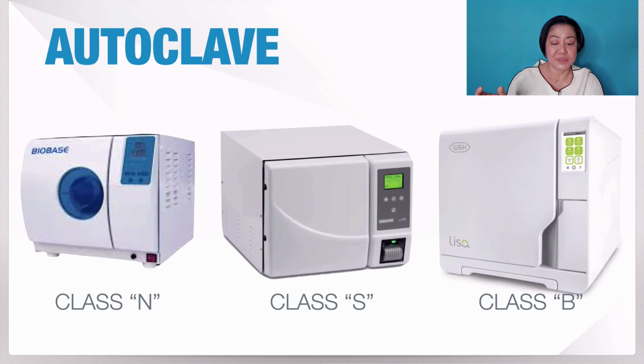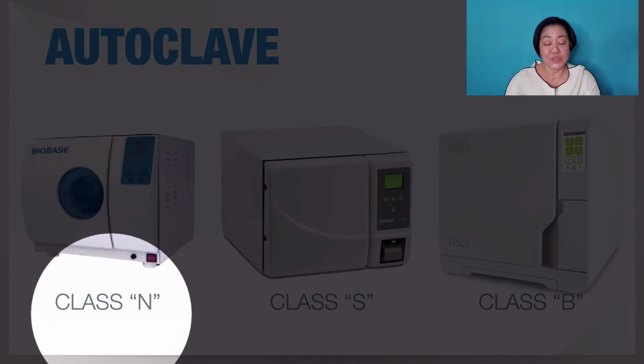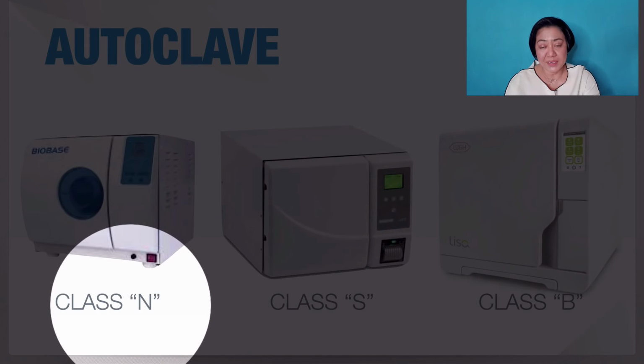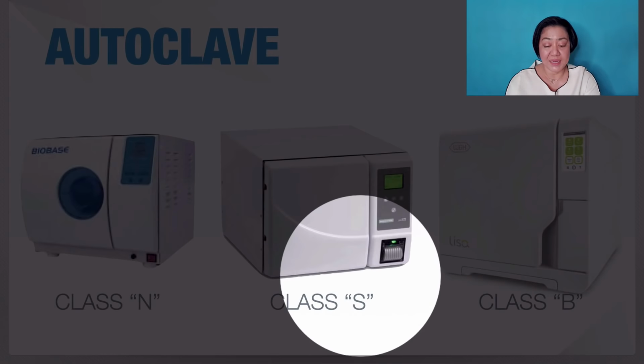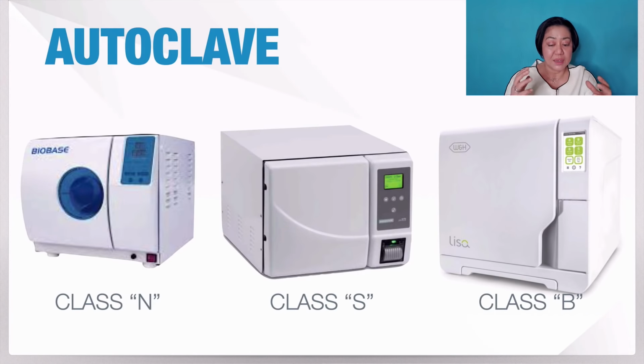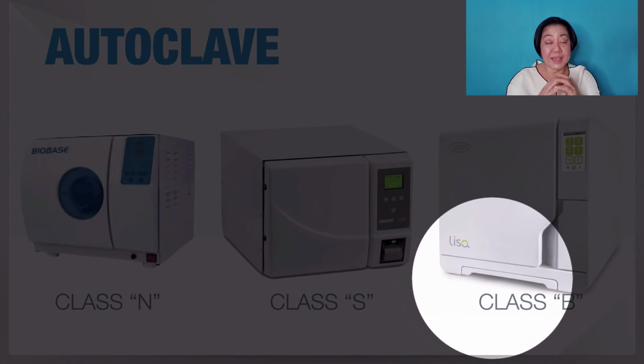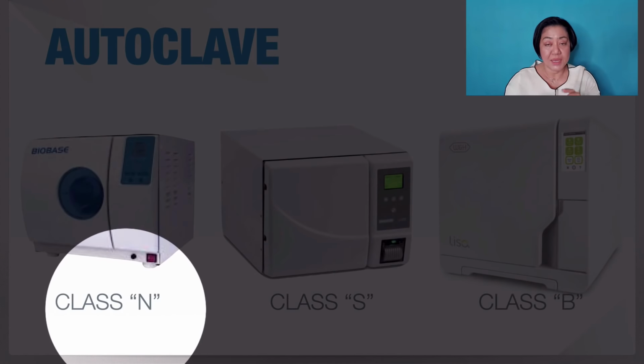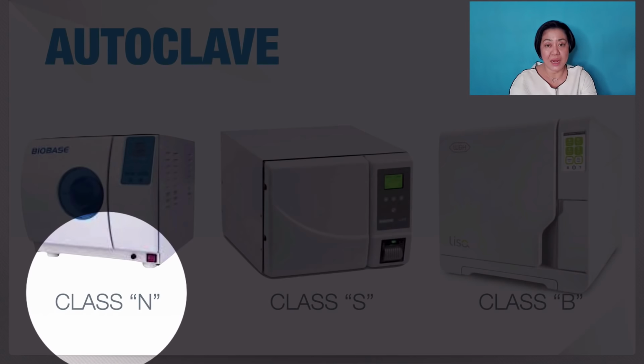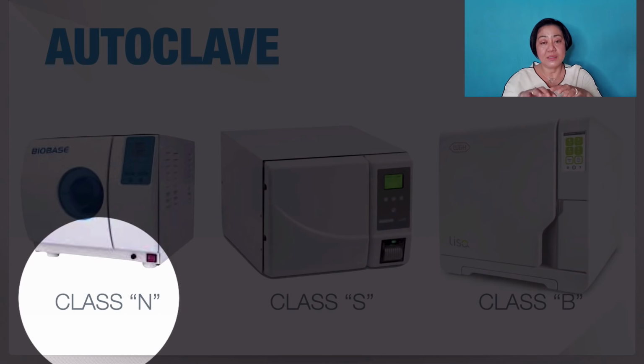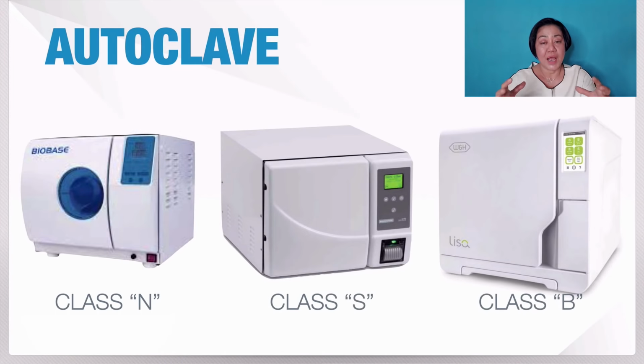These are the different types of autoclave. We have the Class N, which is the most common globally, especially here in the Philippines, Class S, and Class B. Now, of course, the Class B uses vacuum. The Type N cycle is a non-vacuum kind of sterilization. Class N has a lot of limitations. The instruments are better unwrapped when you autoclave with Class N. And the disadvantage of this is once you open the door of the autoclave, your instruments are no longer fully sterilized because your environment and your air is not sterile.